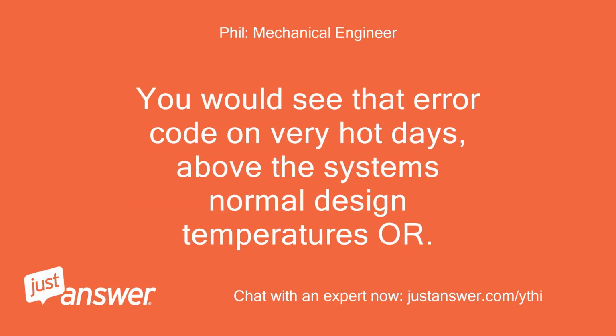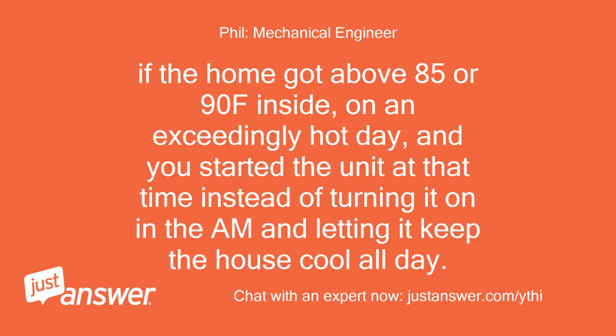You would see that error code on very hot days, above the system's normal design temperatures, or if the home got above 85 or 90 F inside, on an exceedingly hot day, and you started the unit at that time instead of turning it on in the AM and letting it keep the house cool all day.